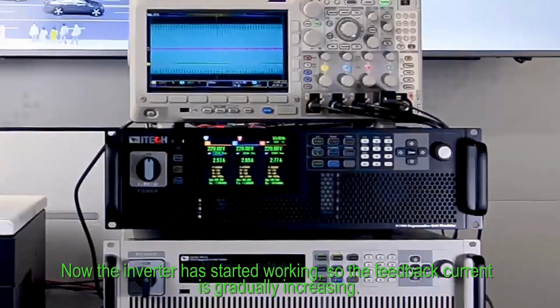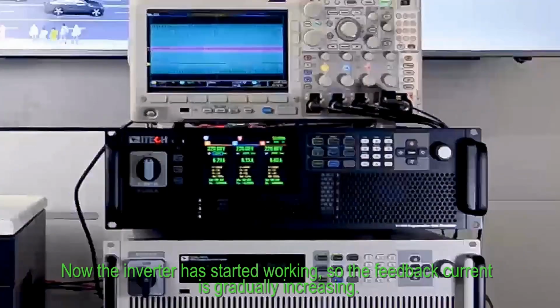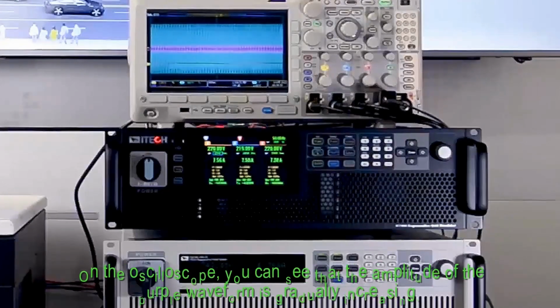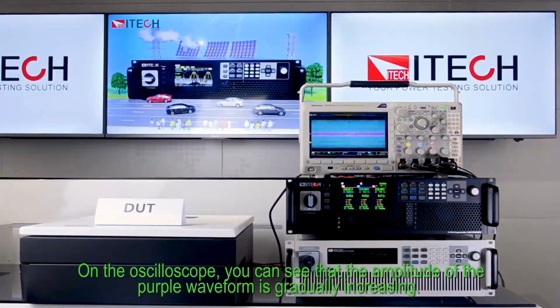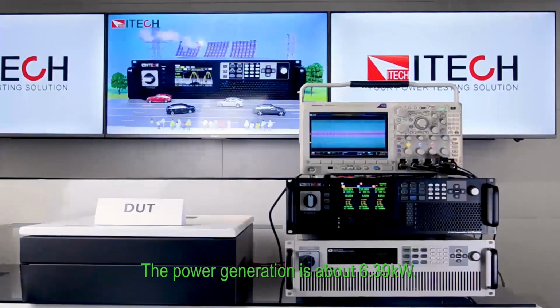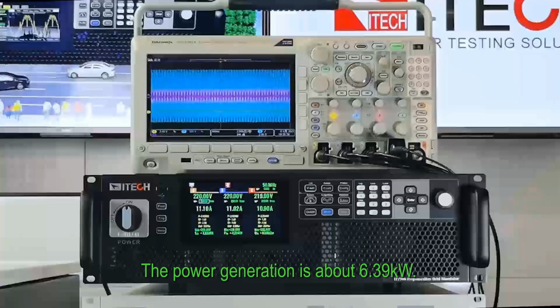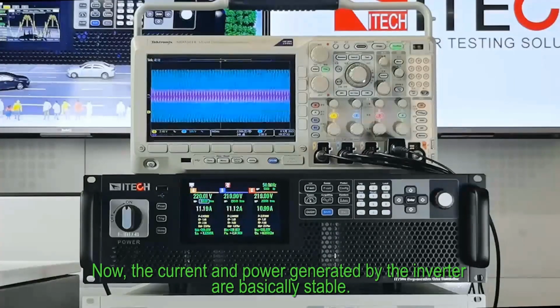Now the inverter has started working, so the feedback current is gradually increasing. On the oscilloscope, you can see that the amplitude of the purple waveform is gradually increasing. The power generation is about 6.39 kilowatts. Now, the current and power generated by the inverter are basically stable.